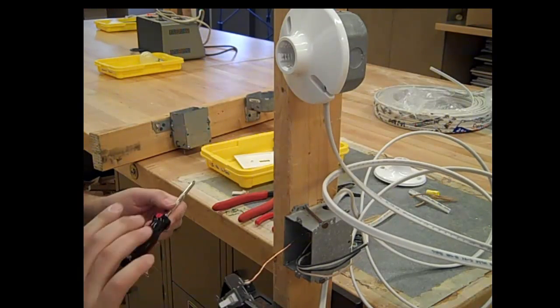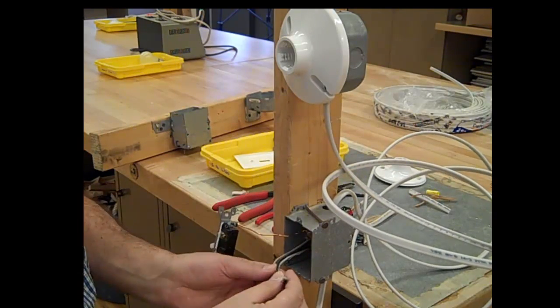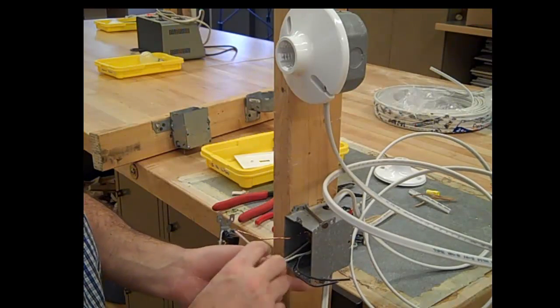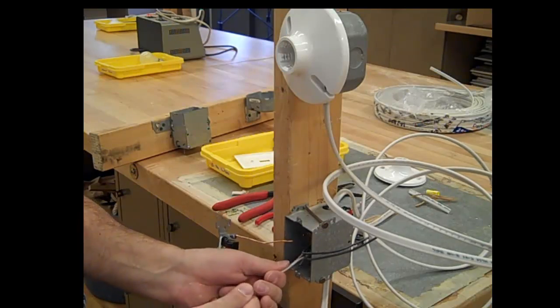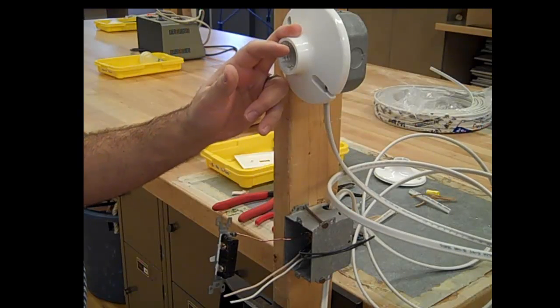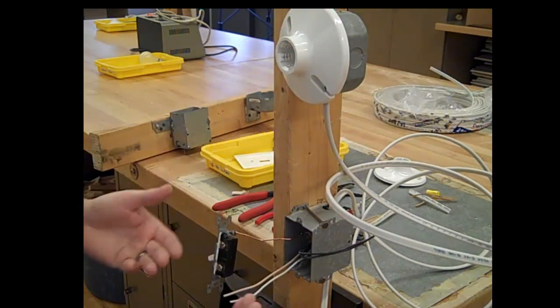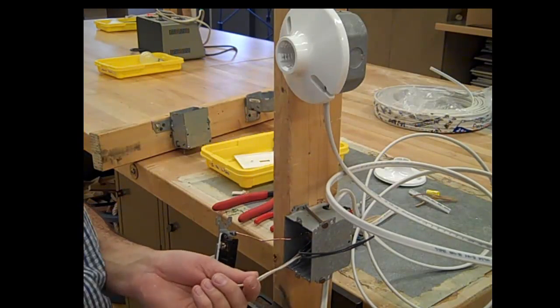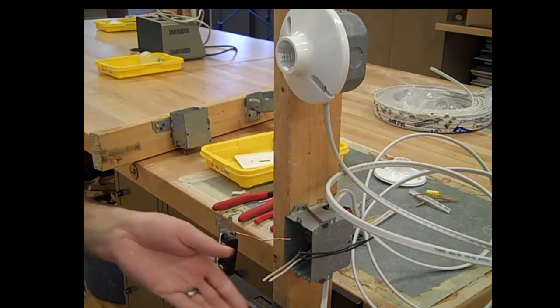When you're tightening these you need to tighten them as hard as you can because they will fall off when you try to jam this back into the box. Next wires I'm going to deal with will be my white wires. The white wires do not get connected to the box or to the switch. They allow the electricity to come back through this area and back to the panel box. I'm going to cut these a little bit shorter just to save on room inside this box.